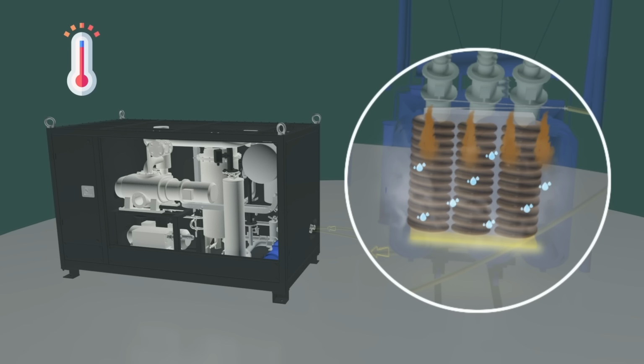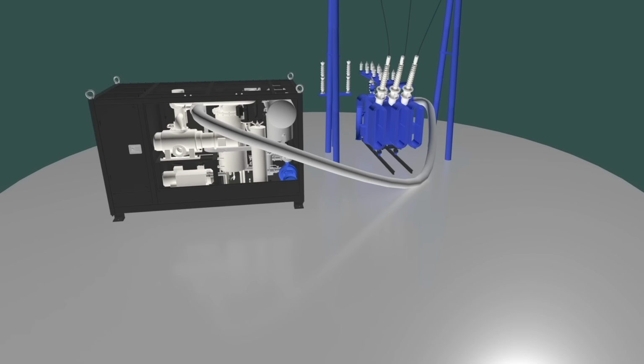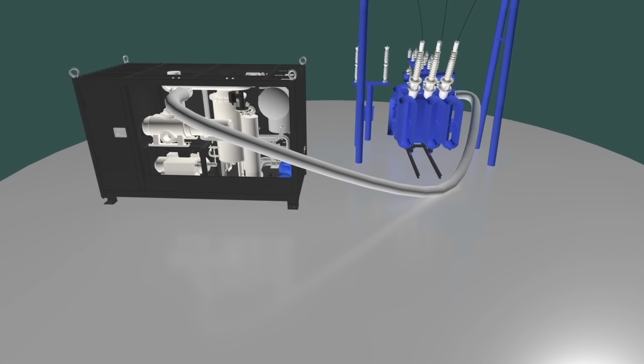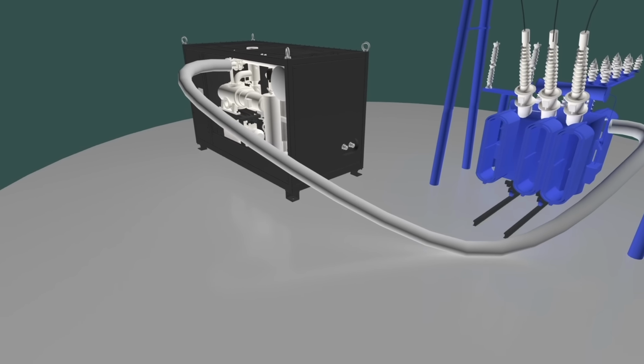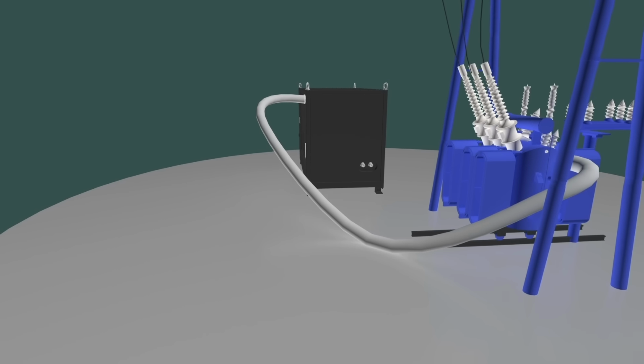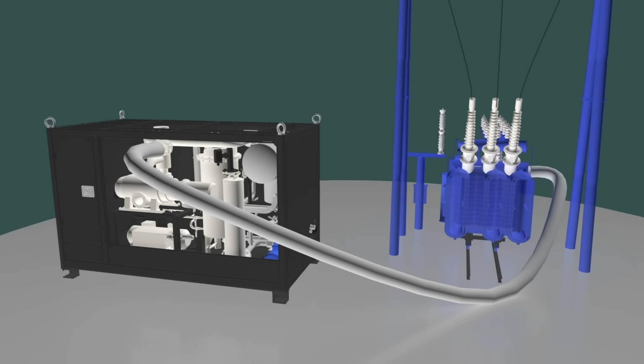Upon completion of the windings warm-up stage, oil feed is stopped, and transformer tank vacuuming begins and lasts a few hours. Transformer oil heating and circulation, as well as transformer tank vacuuming, are performed by a CMM plant equipped with a heater, transfer pumps, and a two-stage vacuum system capable of developing a high vacuum.